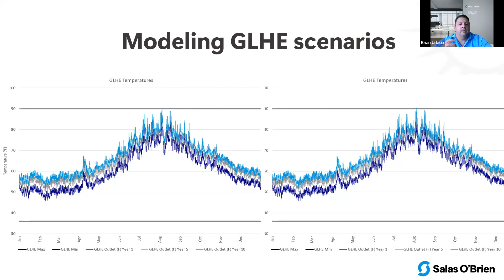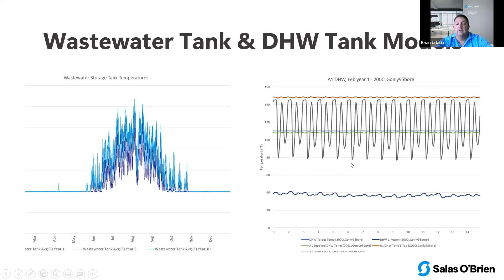This was the wastewater storage tank. So we're modeling that, and you can see we're not using it in the winter - we're using it pretty much strictly in the summer to get rid of heat. And then on the right was our domestic hot water profile. We're showing the storage tanks, the set point, delivery temperatures, and making sure that with this system we can deliver the proper temperatures throughout the year.